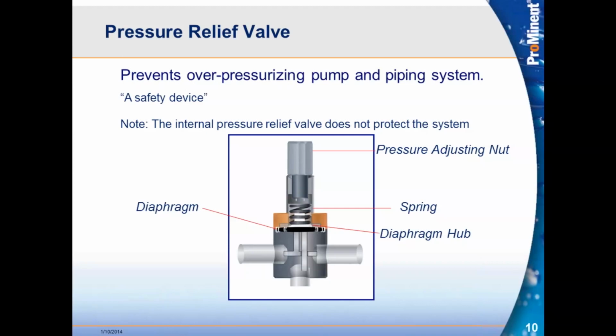You can see here, again, we compress that spring to require a higher force, a higher pressure to open that diaphragm so that it goes out the third port at the bottom. On a pressure relief valve, the 3-port device, the inlet and the outlet, which are 180 degrees apart from one another on the left and right, you can see those. They're not directional. Either one could be the inlet, either one could be the outlet. The inlet and outlet on the back pressure valve are a little bit more directional. So as long as we have that relief is that bottom port.